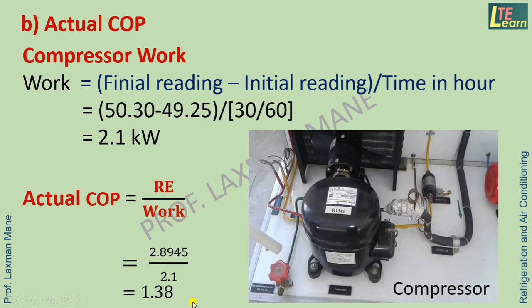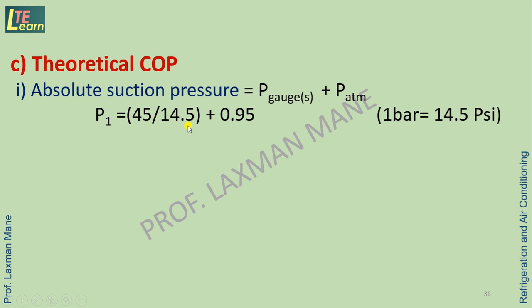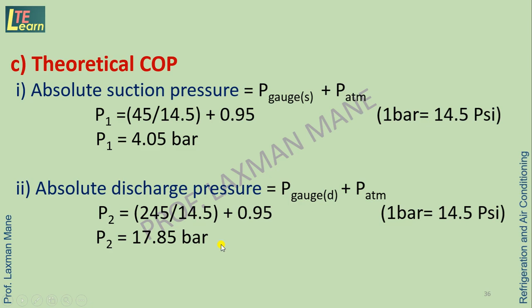To find the theoretical COP, the pressure at inlet and outlet of the compressor is to be taken. So here the absolute suction pressure is required. It is the sum of pressure gauge reading and atmospheric pressure. So at the suction, P1 pressure is equal to pressure in PSI with conversion factor into bar as 14.5, and atmospheric pressure is 0.95. So P1 we get in bar. Similarly we calculate the absolute discharge pressure at the exit of the compressor as P2 in bar.